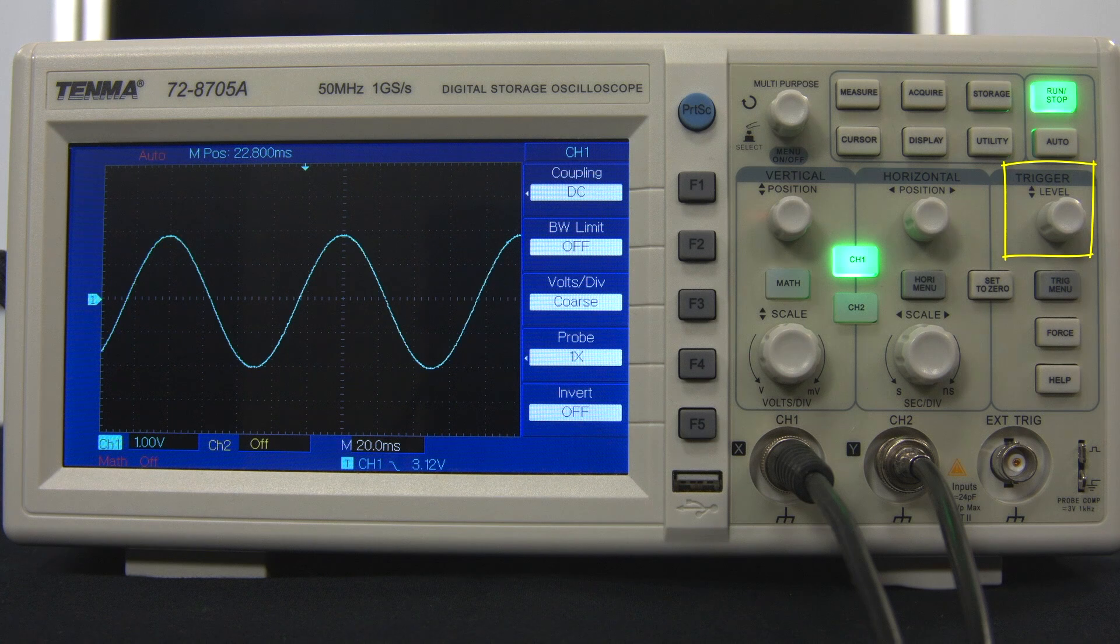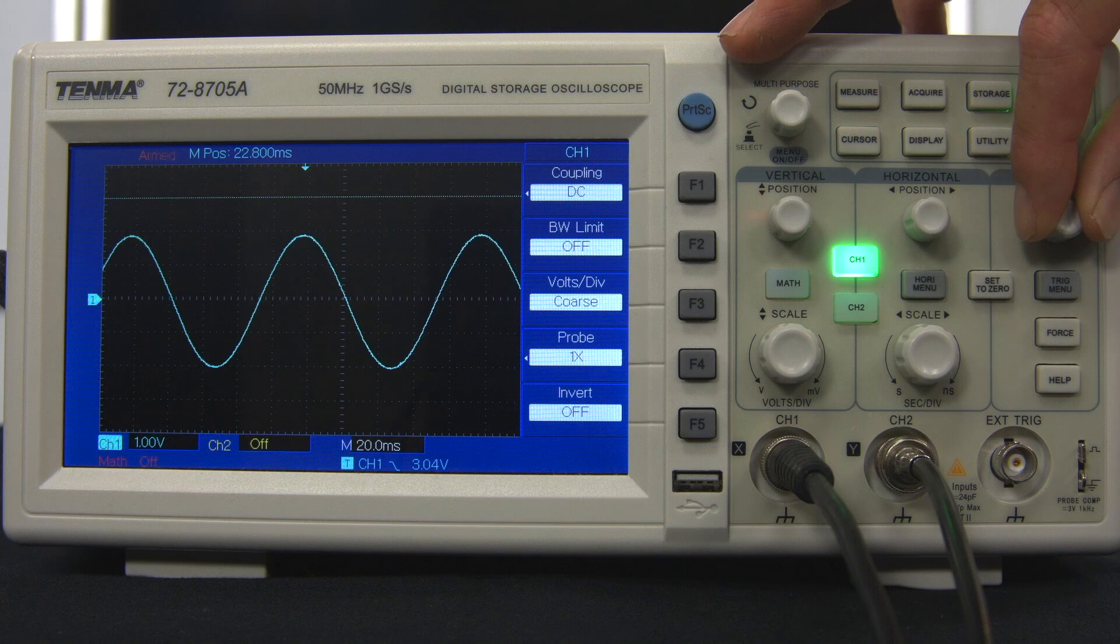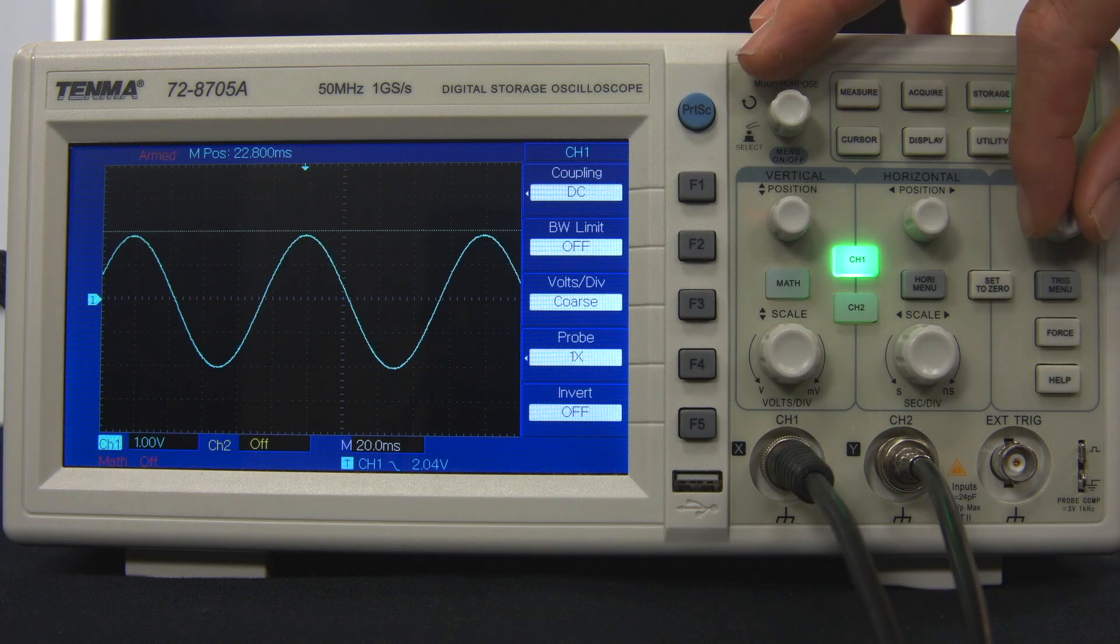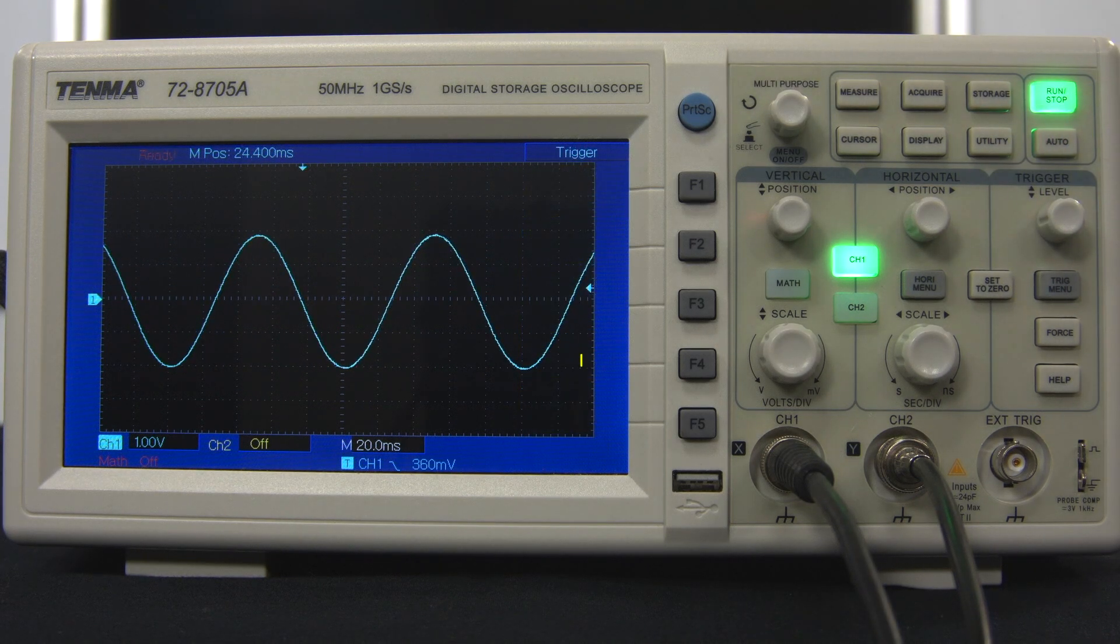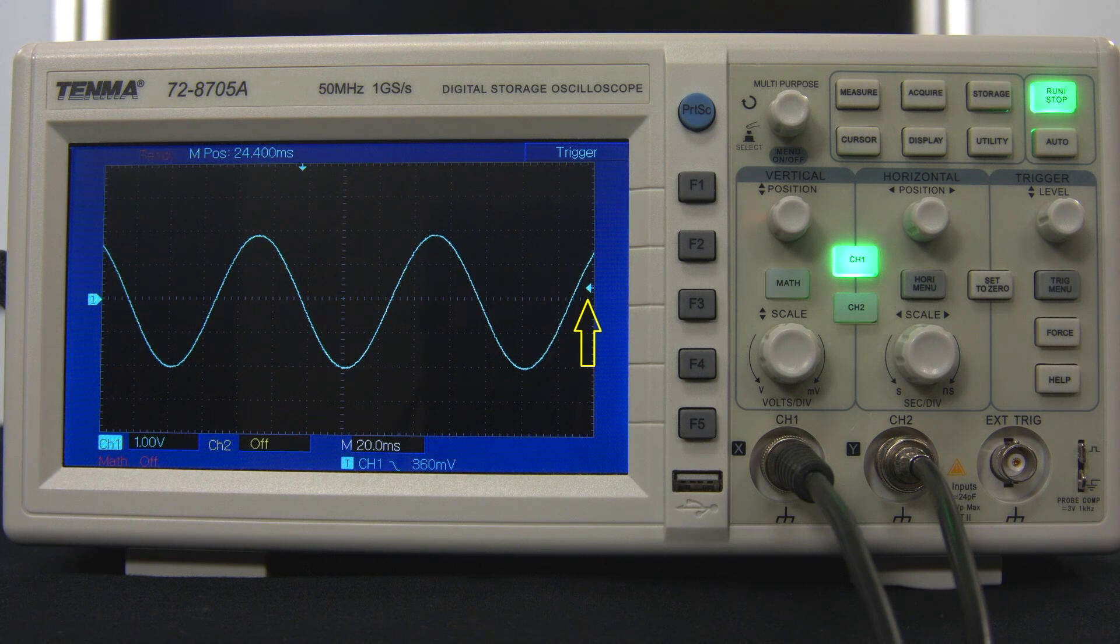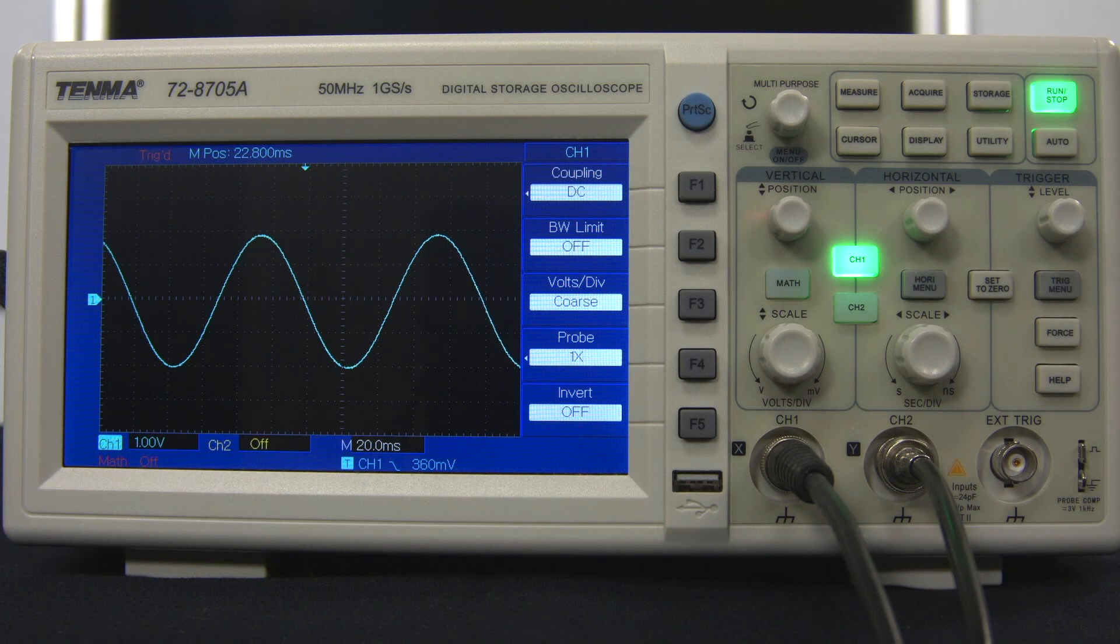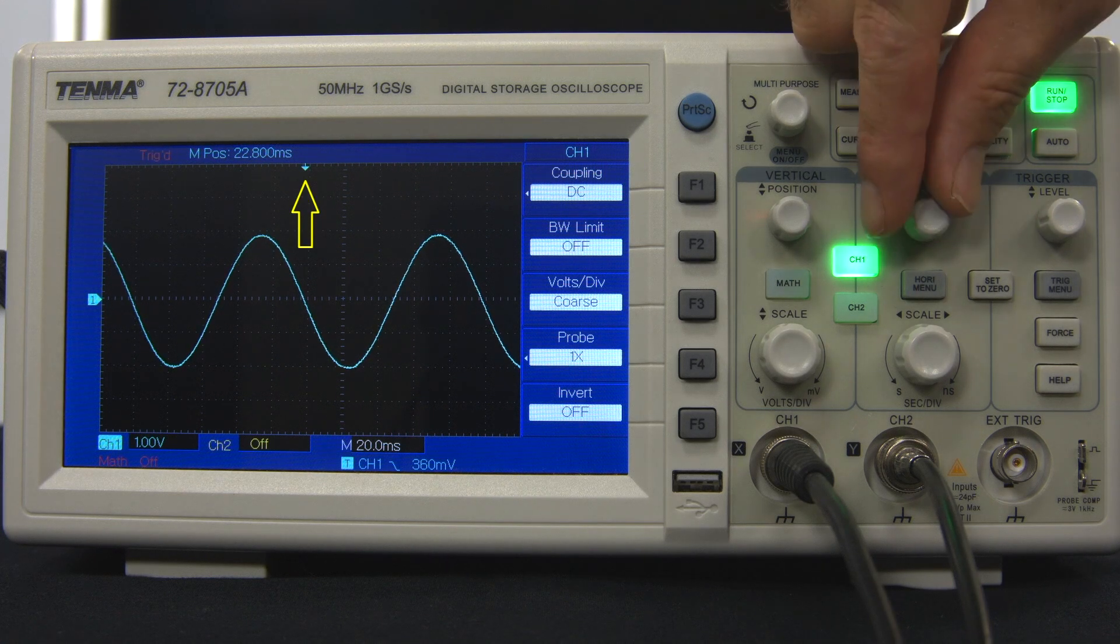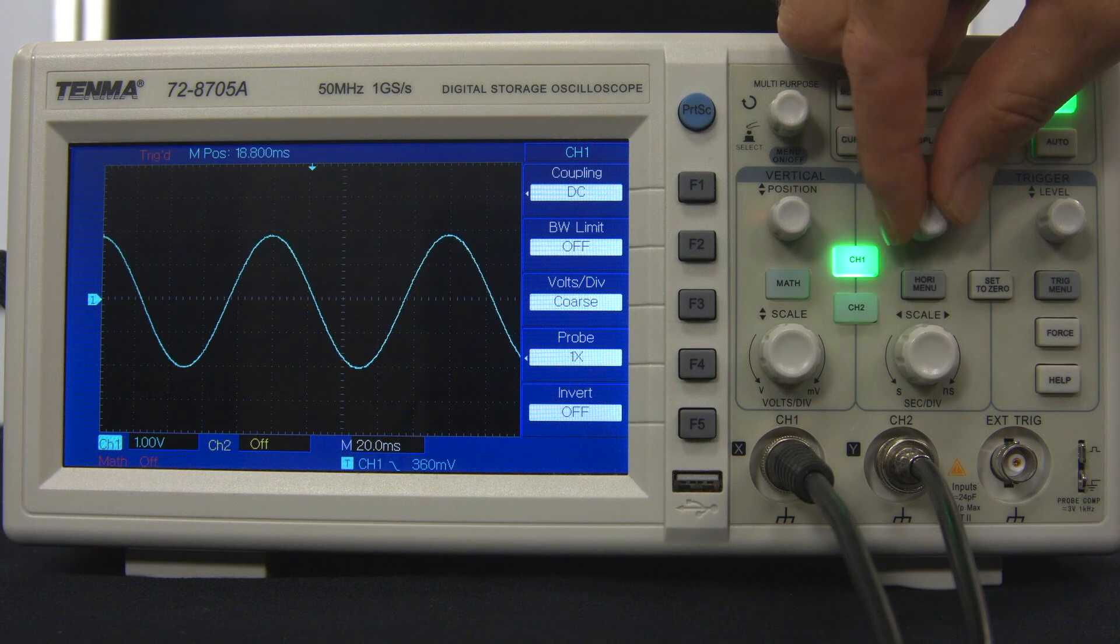The trigger level control changes this voltage setting, and as the knob is turned, a dotted horizontal line shows the trigger voltage value. Once the trigger level matches some part of the signal, the display becomes stable. The trigger level is indicated by the small arrow on the right side of the screen. The trigger point for updating the display also has a location along the horizontal time axis. This is indicated by the small arrow at the top of the screen. When the horizontal position is adjusted, it is this trigger location that moves left or right.